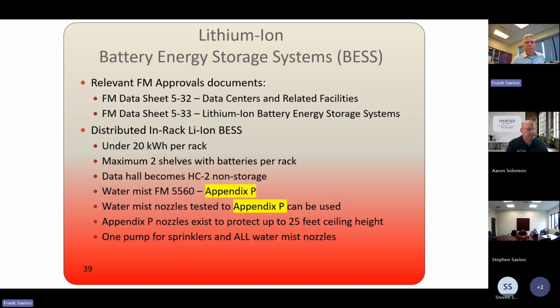Right. So the Appendix P nozzles can protect up to 25 feet. And the other thing that's noteworthy is one pump for sprinklers and the mist. So if you have a battery energy storage system and you have to put sprinklers in there to get the 0.3 density and the rest of your building is going to be water mist, you can just size your pump to deliver the GPM that you need, but also the pressure that you need. So you can have a hybrid system where you've got sprinklers in some areas and water mist in other areas. That's the key point here.